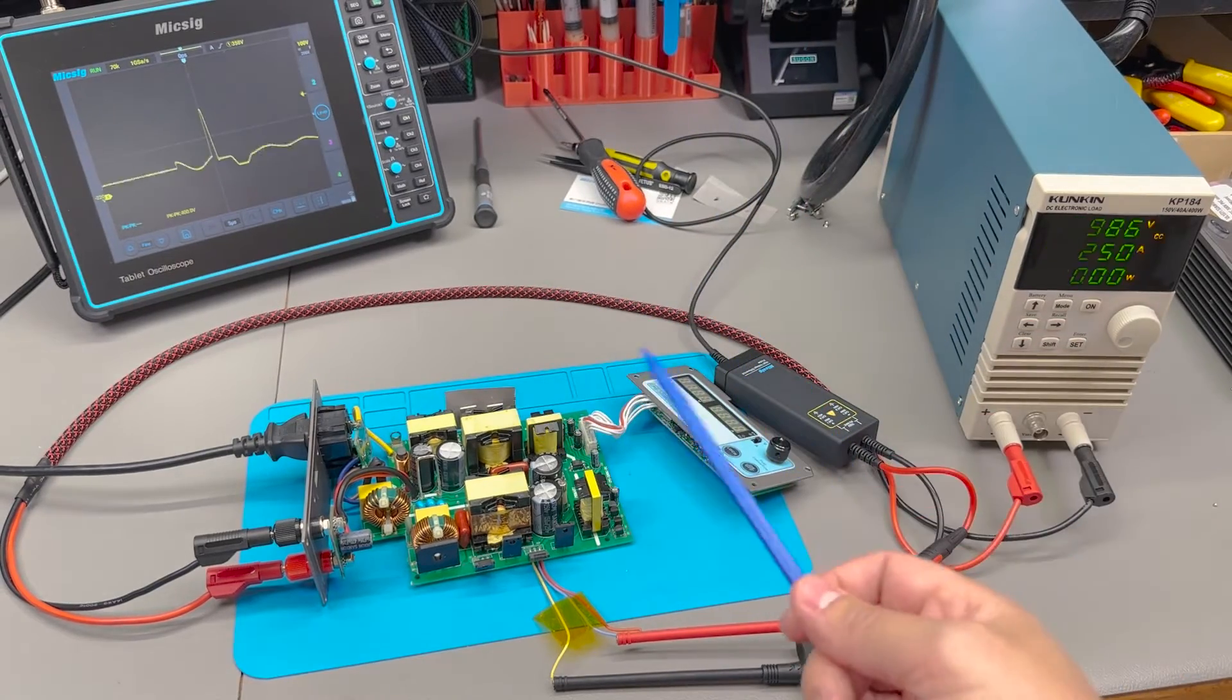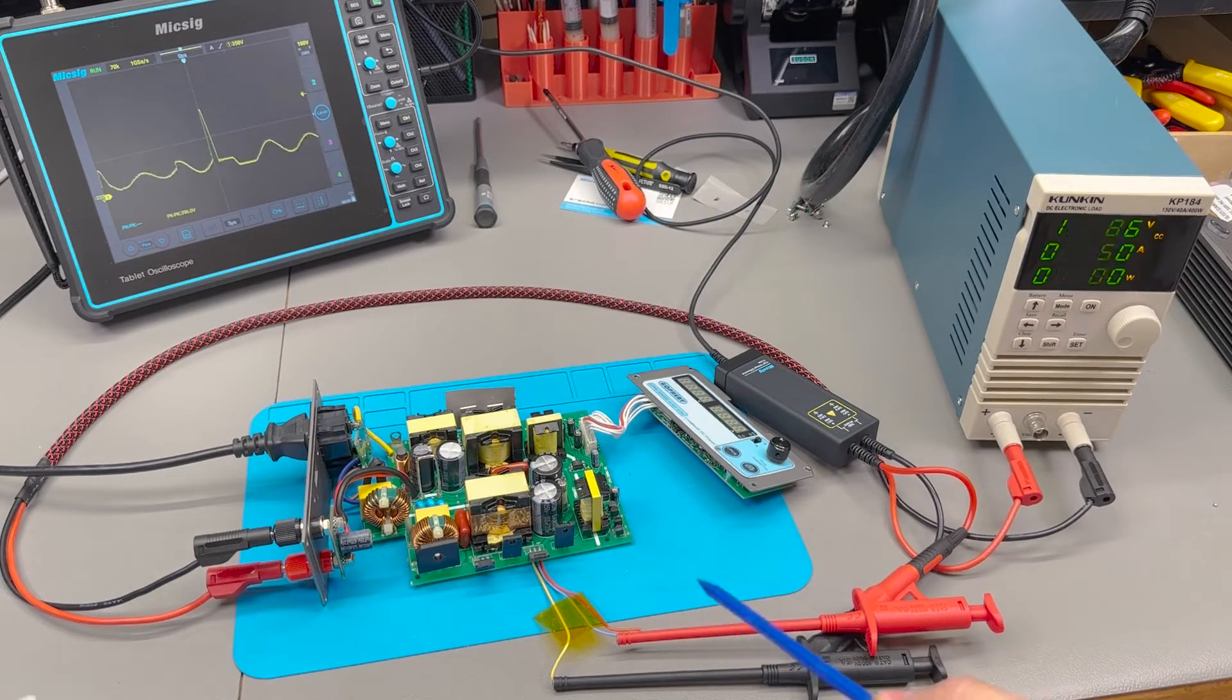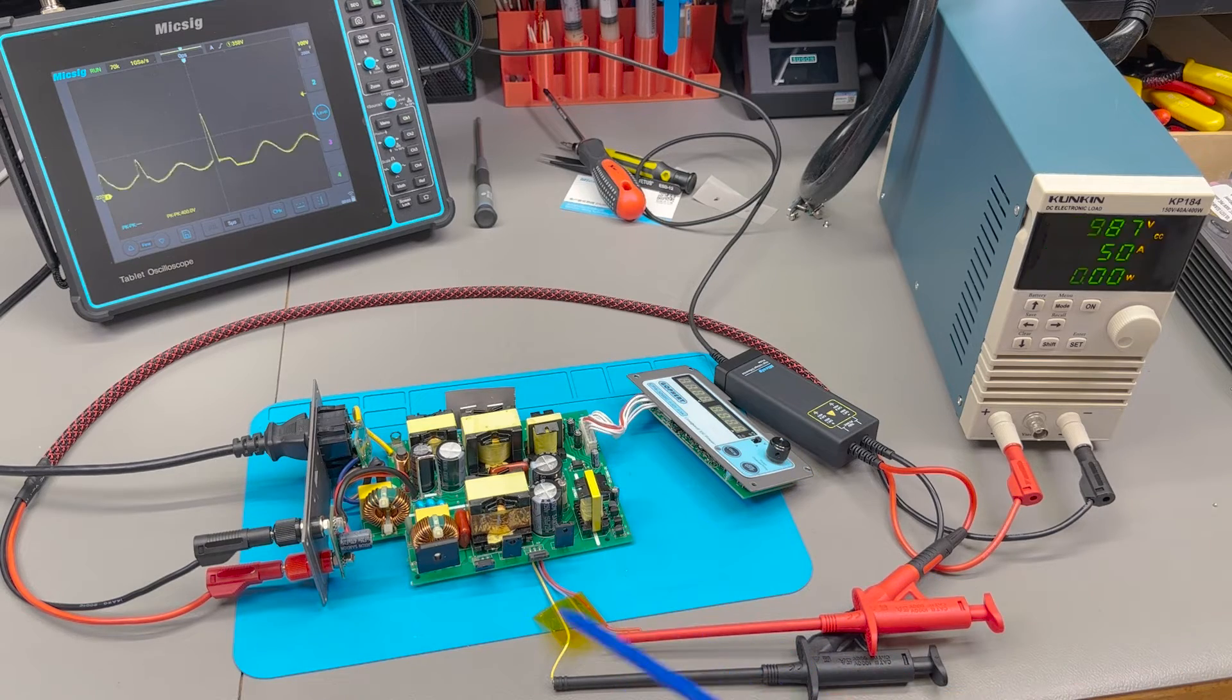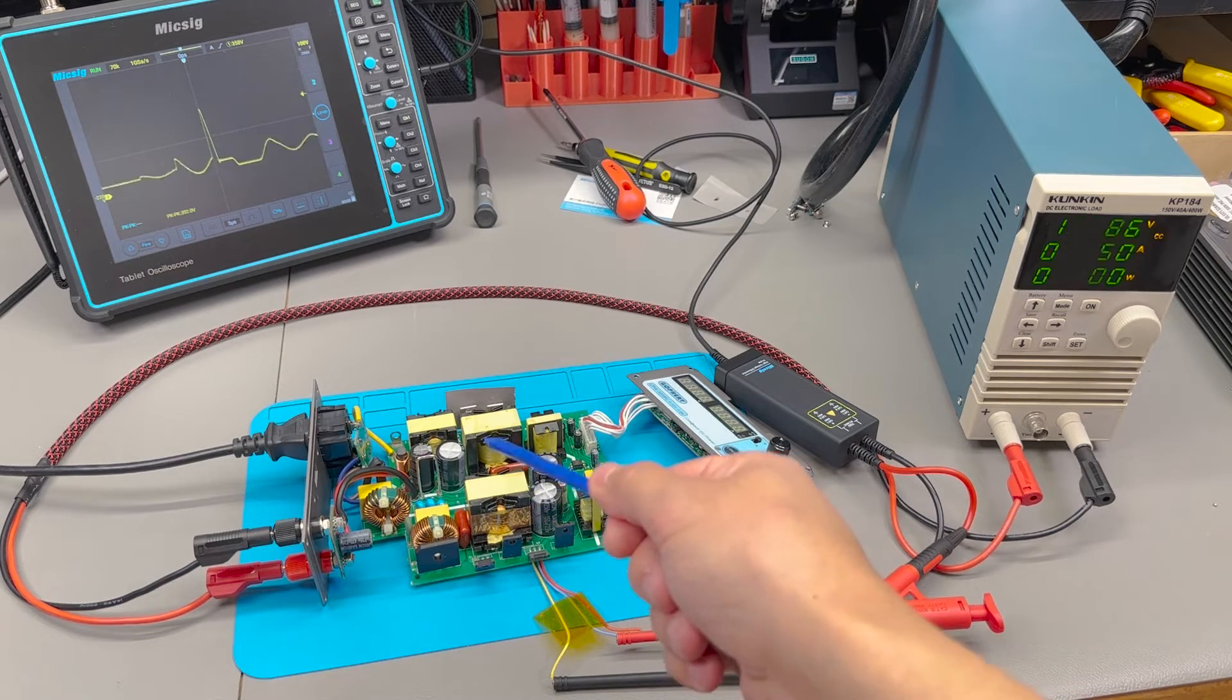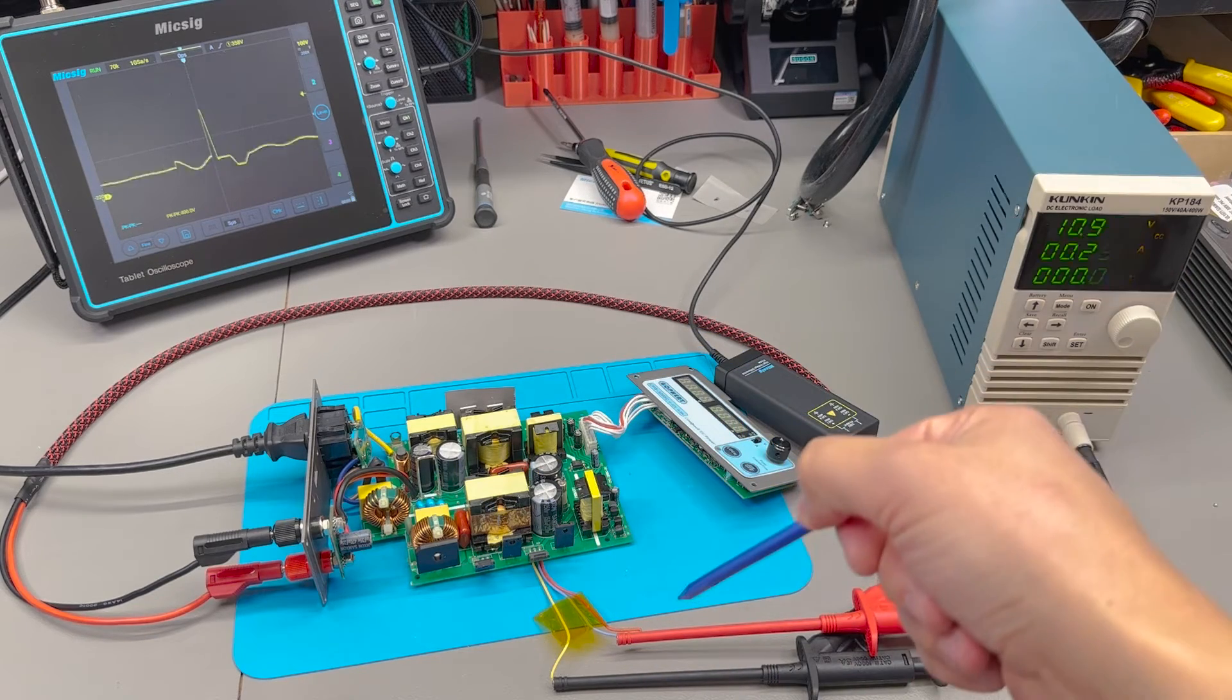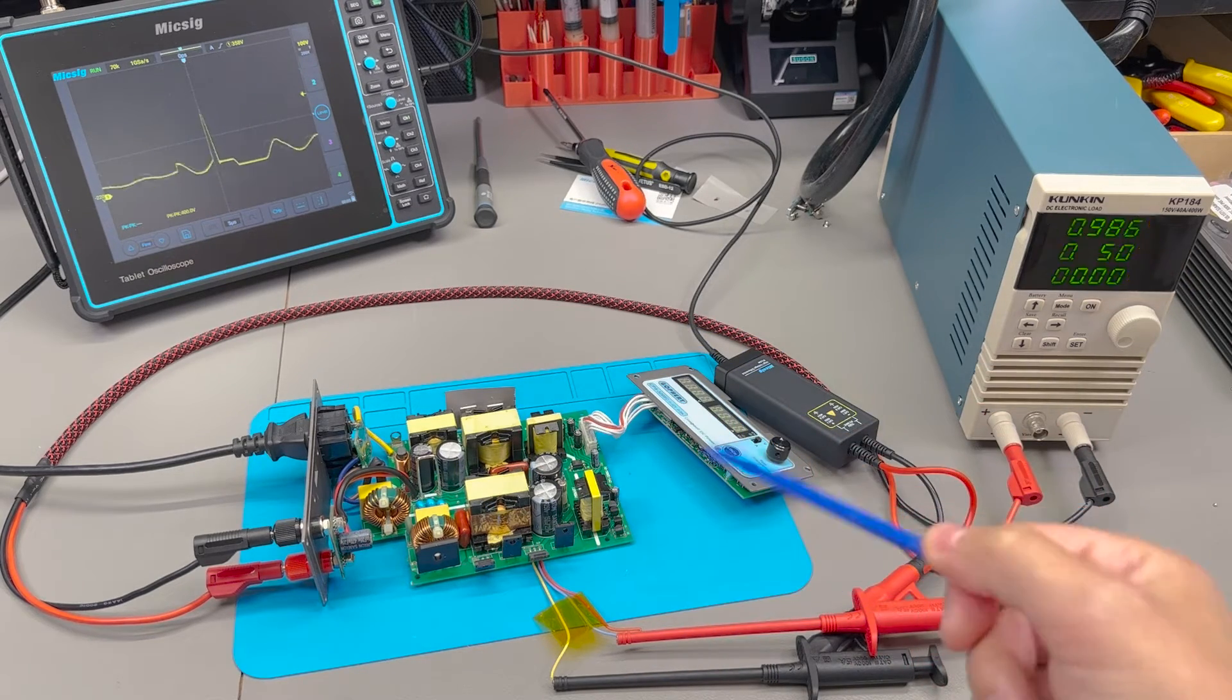You wouldn't be able to safely do this with a classic oscilloscope probe because you might accidentally short the measured signal to mains earth through your ground clip but with this there is no risk of that happening.